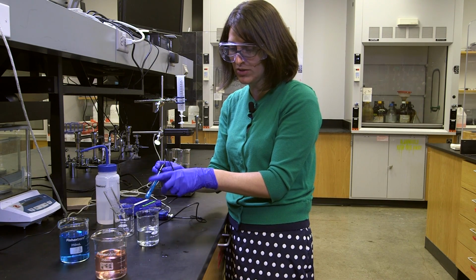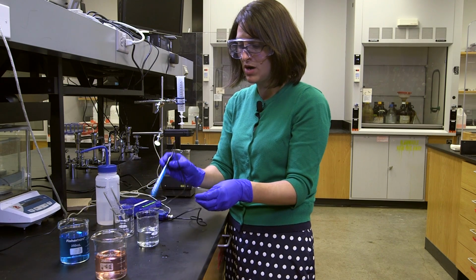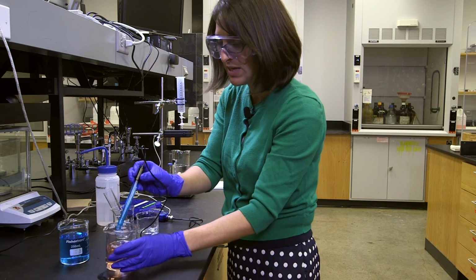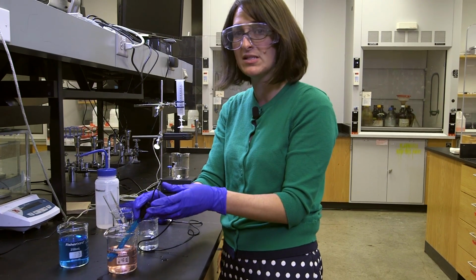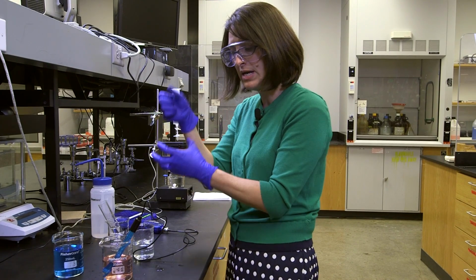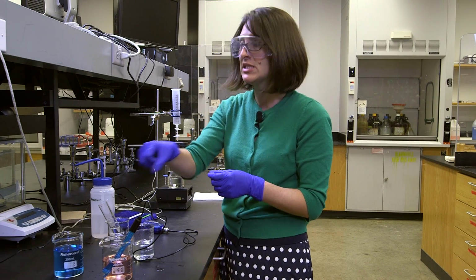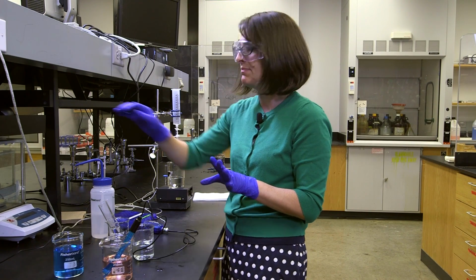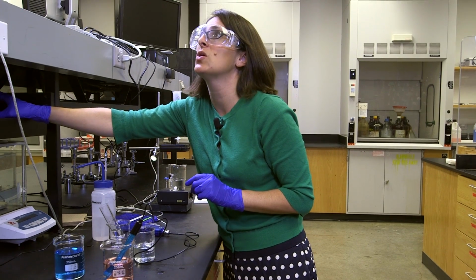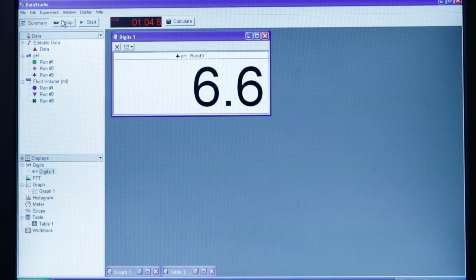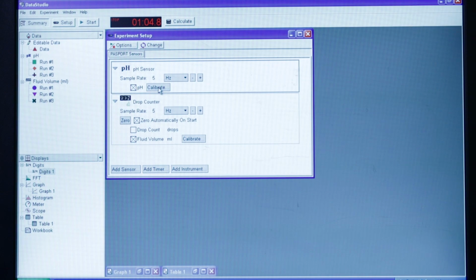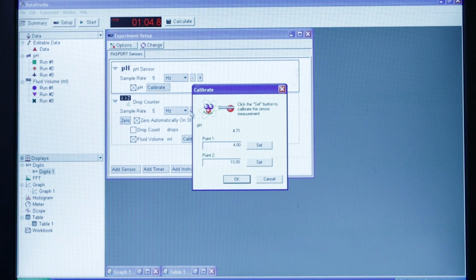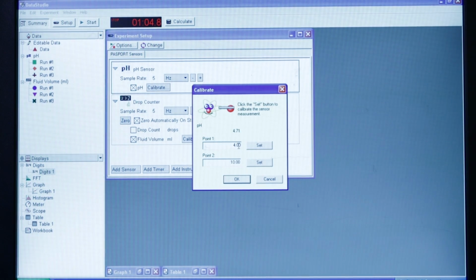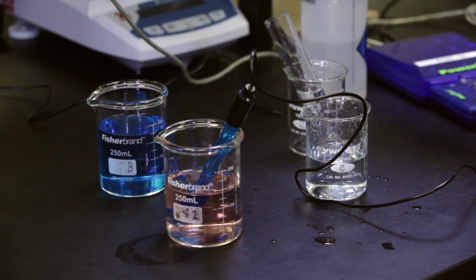I can tap a little bit just gently to get some of that liquid off, because I'm going to put it in this pink solution as a pH 4 buffer. It's a standard. I poured it from my standard jug into my beaker, so I know it's all set. So I have to calibrate. So I have to go up to the computer. I'm going to click Setup, and then I'm going to click Calibrate, and there will be two points. So point number 1 is my 4, my low pH, and this is a pH 4.